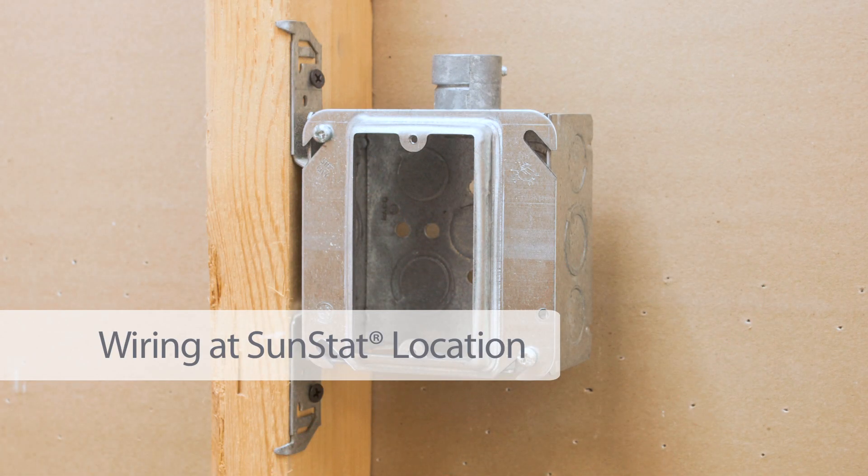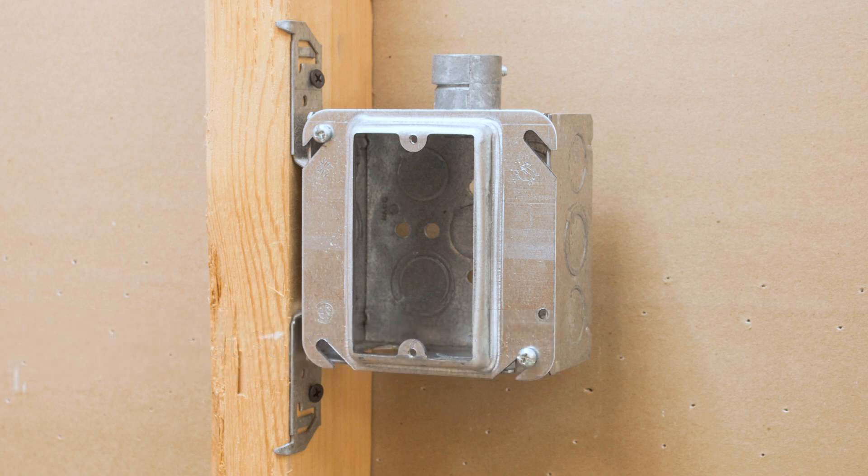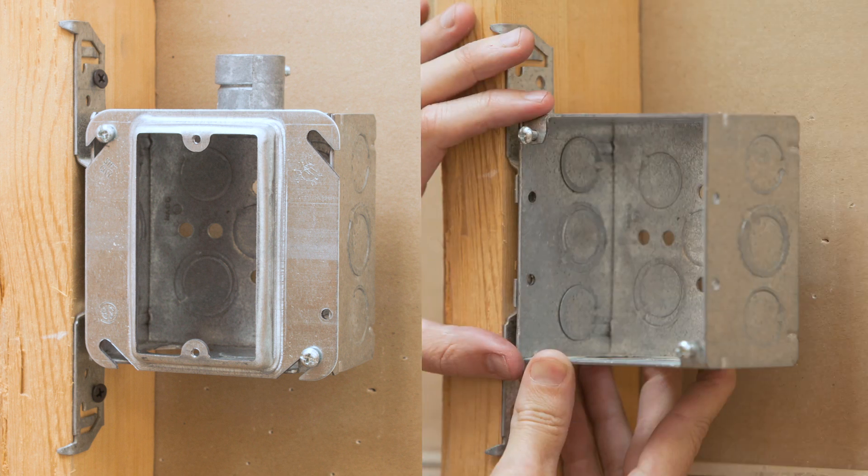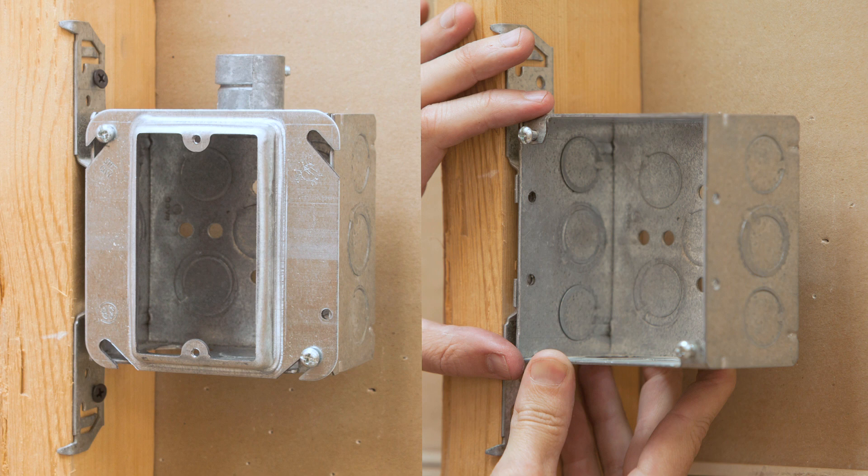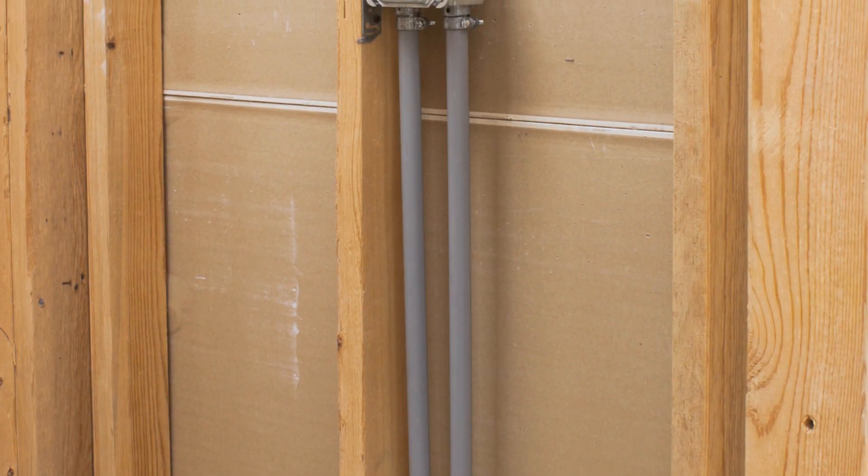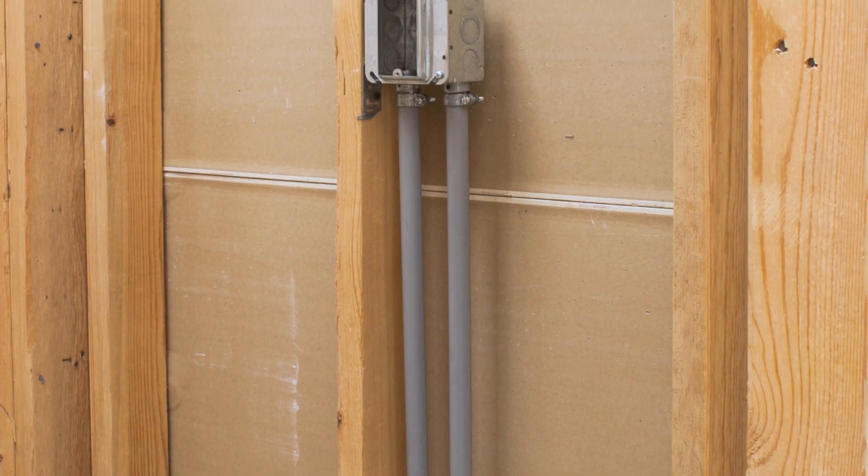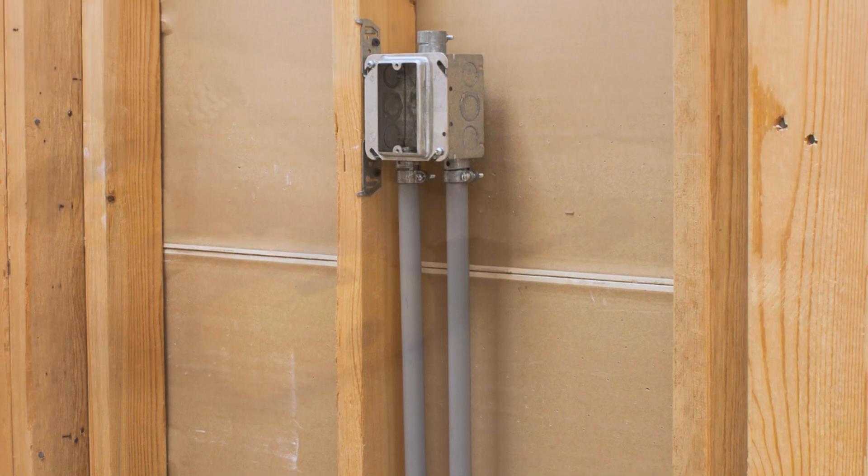Select the thermostat location and have your electrician install the appropriate electrical box. Make sure it's large enough to meet the box fill requirements of your local code. An extra deep box or a 4 by 4 inch deep box with a mud ring are commonly used. Conduit may be required to protect the wiring from potential damage through the wall. Consult your local code.